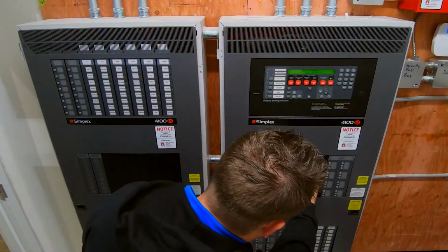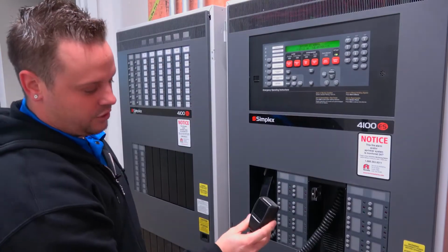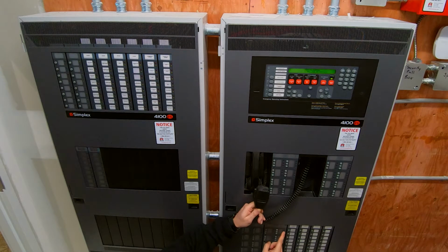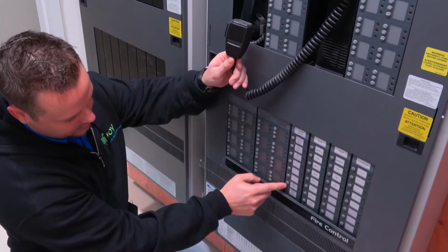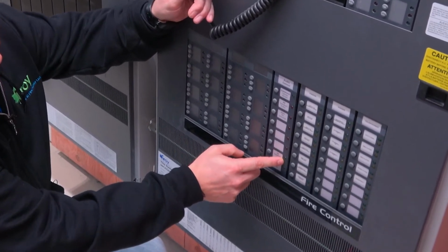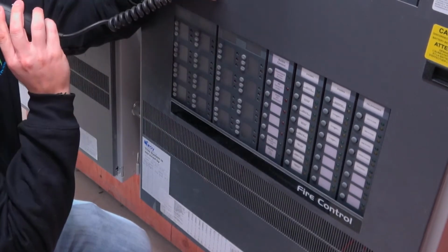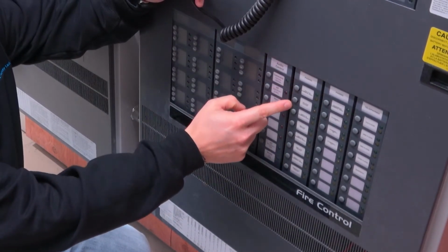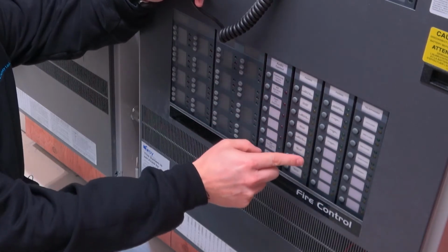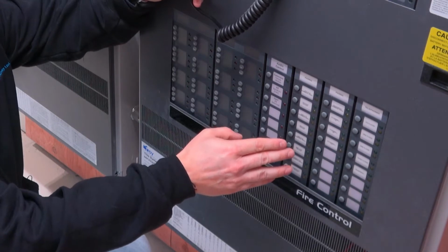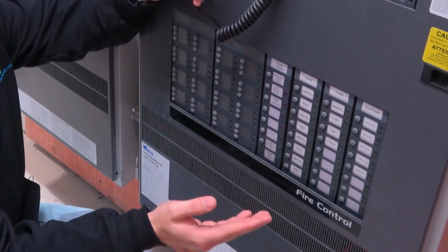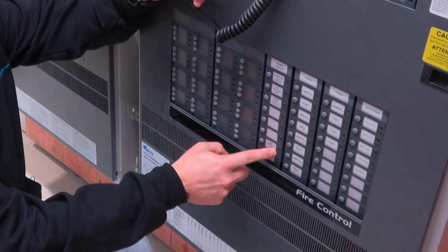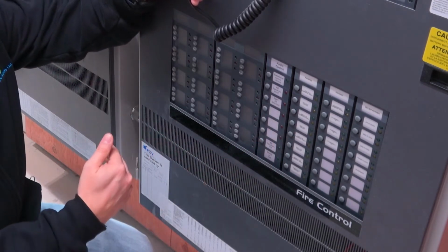We're going to move down here. This is your mic for your speakers in your building. Basically, to activate your mic is down on the bottom here. Once your mic is up and running, you press your all speakers talk. This is going to illuminate green, and then you're going to be able to key the mic and make your announcement. You also can isolate the floors and suites. As you can see, 4th floor common, 4th floor suites, 3rd floor common, so forth. Not really used during maintenance, more used during the annual inspection that we come in for. So basically what the maintenance guy or people on site would be using would be the all speakers talk. And that's just to communicate what's happening with the panel and if the fire department is giving the all clear.